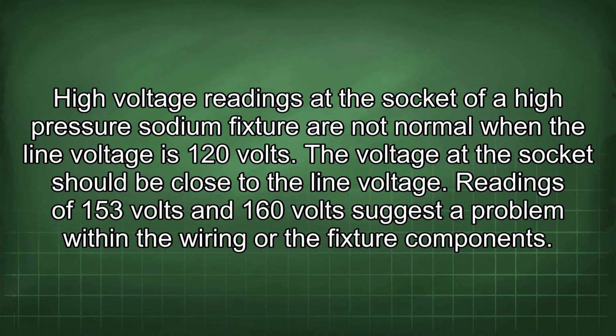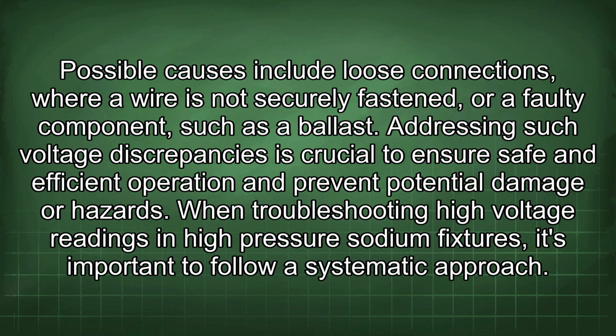High voltage readings at the socket of a high-pressure sodium fixture are not normal when the line voltage is 120 volts. The voltage at the socket should be close to the line voltage. Readings of 153 volts and 160 volts suggest a problem within the wiring of the fixture component. Possible causes include loose connections where a wire is not securely fastened, or a faulty component such as the ballast. Addressing such voltage discrepancies is crucial to ensure safe and efficient operation and prevent potential damage or hazards.